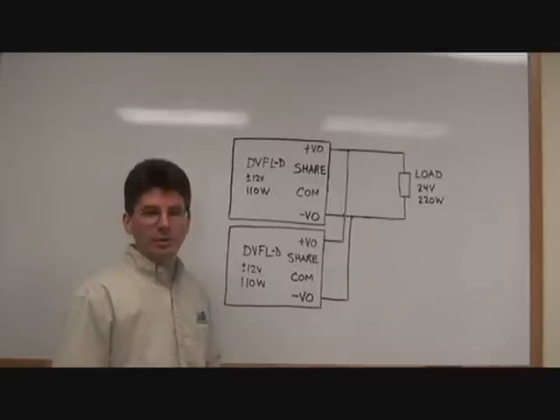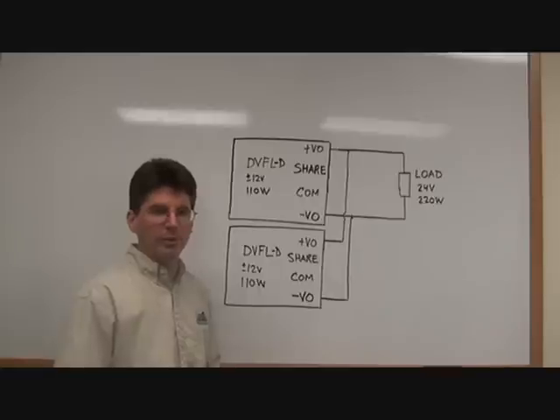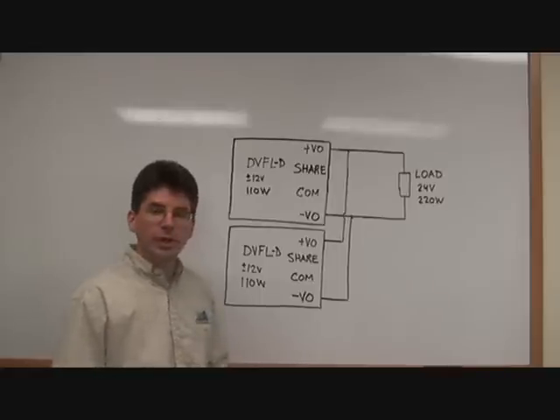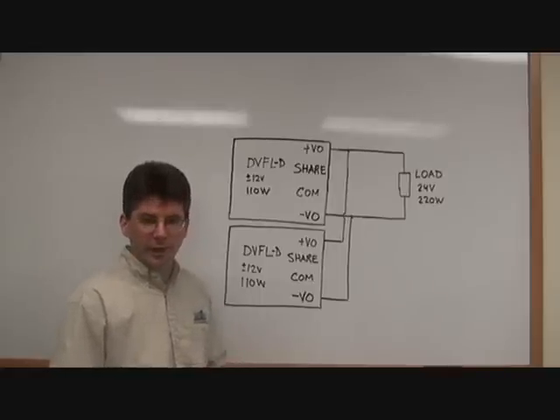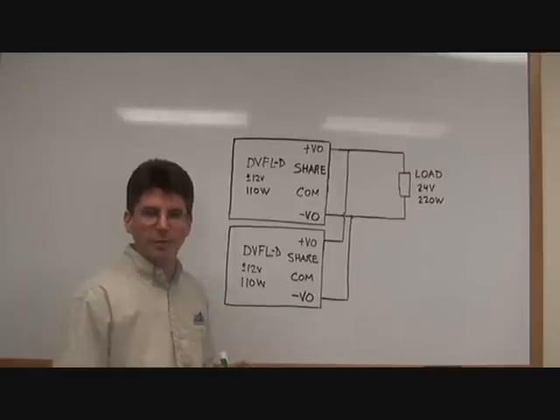The current sharing function is also available on the DVFL dual output converter. Since the current sharing function works on total output current, it's really not useful to share a plus 12 and a minus 12, for example, individually.